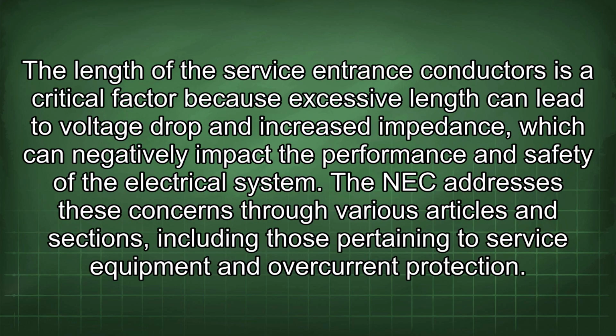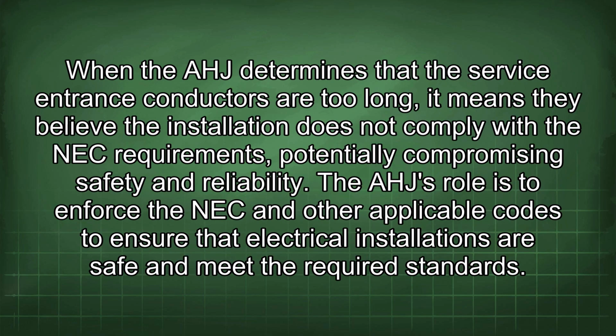The length of the service entrance conductors is a critical factor because excessive length can lead to voltage drop and increased impedance, which can negatively impact the performance and safety of the electrical system. The NEC addresses these concerns through various articles and sections, including those pertaining to service equipment and overcurrent protection. When the AHJ determines that the service entrance conductors are too long, it means they believe the installation does not comply with the NEC requirements, potentially compromising safety and reliability.